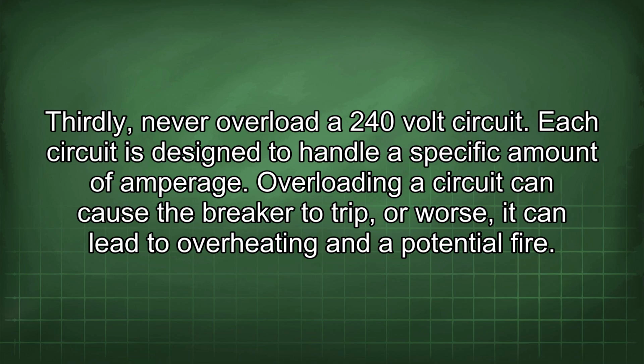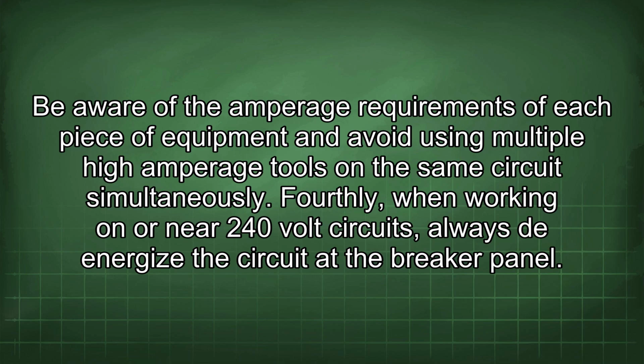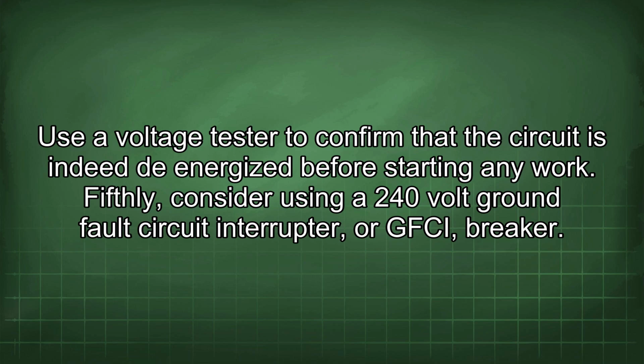Overloading a circuit can cause the breaker to trip, or worse, it can lead to overheating and a potential fire. Be aware of the amperage requirements of each piece of equipment and avoid using multiple high amperage tools on the same circuit simultaneously. Fourthly, when working on or near 240-volt circuits, always de-energize the circuit at the breaker panel. Use a voltage tester to confirm that the circuit is indeed de-energized before starting any work.